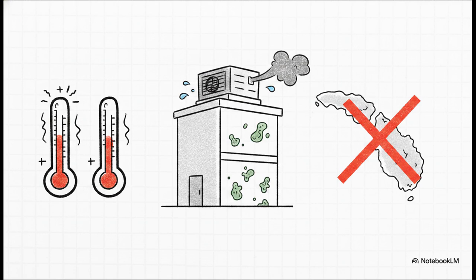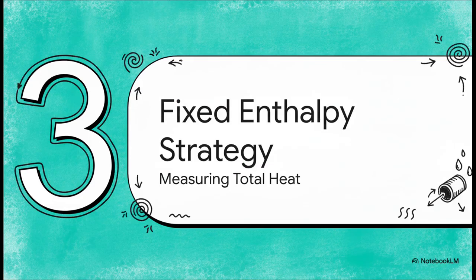In fact, because of those doubled inaccuracies and the serious mold risks from unchecked moisture, strict energy standards like ASHRAE 90.1 actually flat out ban this two-sensor strategy in warm, moist climates, stretching all the way from zone 1A to 6A. It just forces the mechanical cooling system to work way too hard, fixing the damp air it accidentally invited inside. All right, so how do we finally defeat our hidden villain of humidity?